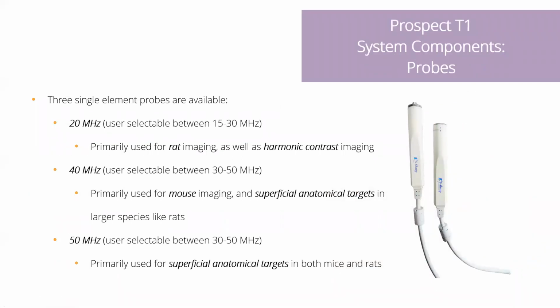There are 3 different probes available with the system: a 20 megahertz, 40 megahertz, and 50 megahertz probe. Traditionally, the 20 megahertz probe is used for rat imaging, as well as harmonic contrast imaging. The 40 megahertz probe is used for mouse imaging of superficial targets as well. And the 50 megahertz is very much used for superficial anatomical targets. When we talk about a probe being used for mouse or rat, that's just their traditional use.